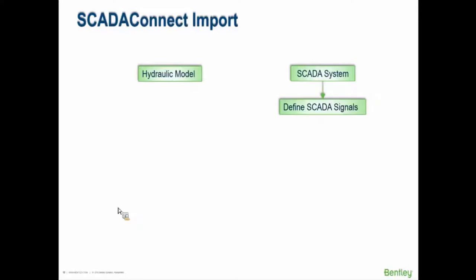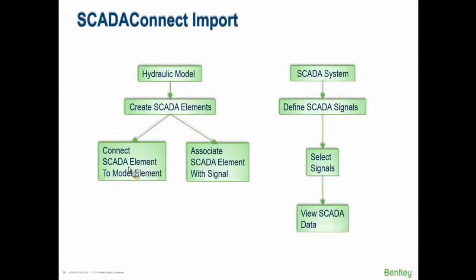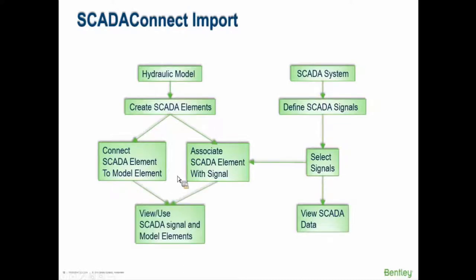How does SCADA Connect import work? You figure out which signals you want from the SCADA system, because most signals you don't need — you don't care about the temperature in the pump station or intrusion alarms. You select the signals you really want, set up the connection, and look inside the SCADA system or file to see those values. Then you build the SCADA elements, connect them to model elements, and associate each SCADA element with a signal. Now you can compare model results to SCADA signals, which is a very powerful thing.